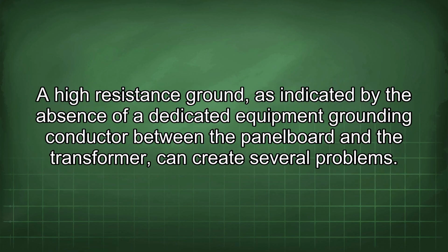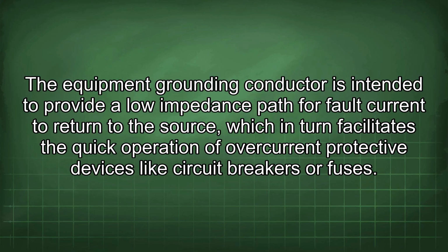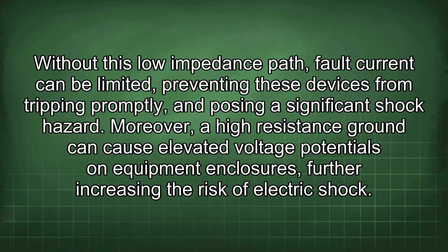A high resistance ground, as indicated by the absence of a dedicated equipment grounding conductor between the panel board and the transformer, can create several problems. The equipment grounding conductor is intended to provide a low impedance path for fault current to return to the source, which in turn facilitates the quick operation of overcurrent protective devices like circuit breakers or fuses. Without this low impedance path, fault current can be limited, preventing these devices from tripping promptly and posing a significant shock hazard.